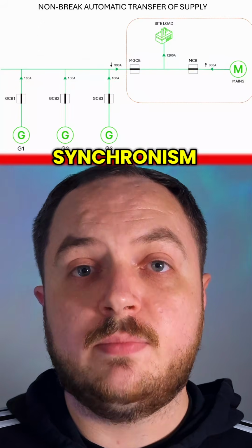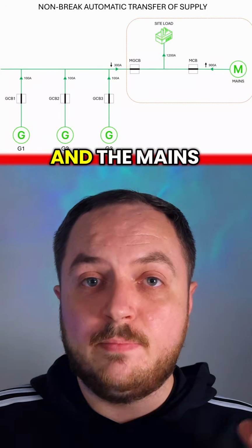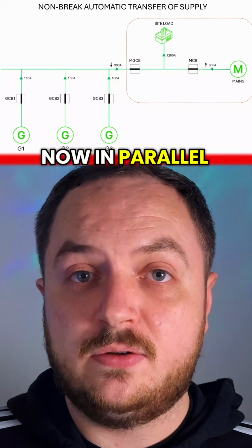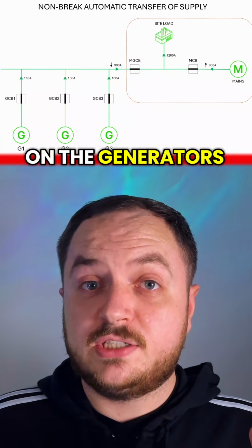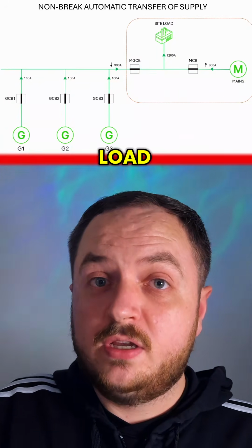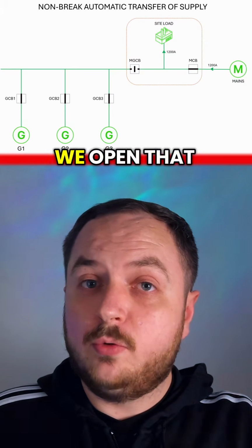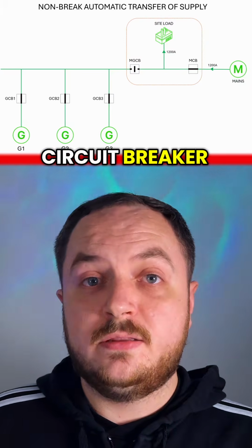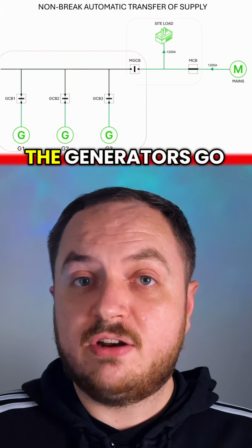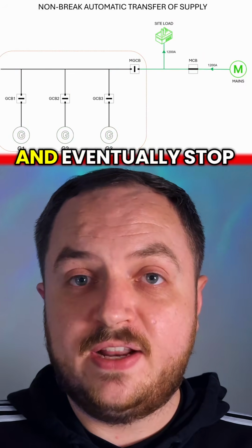Once we're in synchronism, then we can close the mains breaker, and the mains and generators are now in parallel. We then ramp down the load on the generators, which means the mains takes more load. Eventually, when we get to a low level, we open that master generator circuit breaker. The site's now back on mains, the generators go into a cool down and eventually stop.